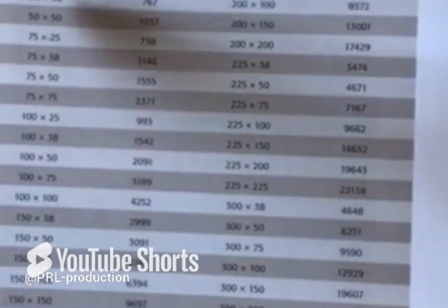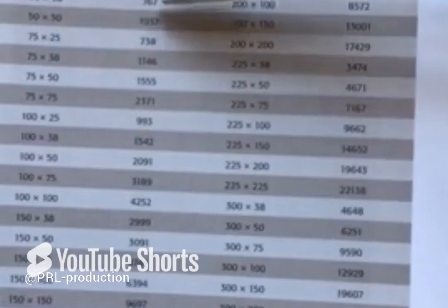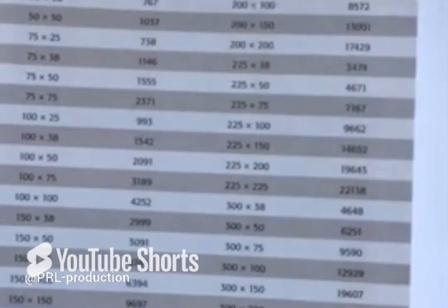So as you can see from the very top, a 50 by 38 trunking would have a factor of 767. So I can do exactly the same as I did in my conduit calculations, but this time making sure you use table E5 and E6 to get your solutions. Now I'll set some questions up separately to this video, and then you can have a go at those and email them to me.